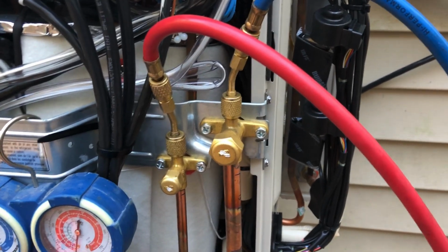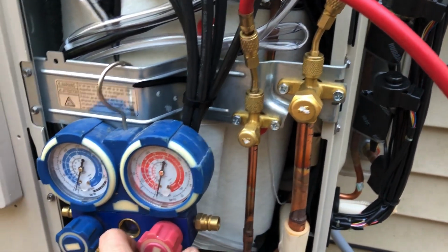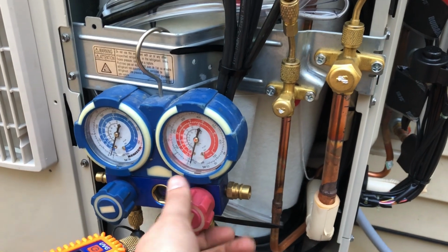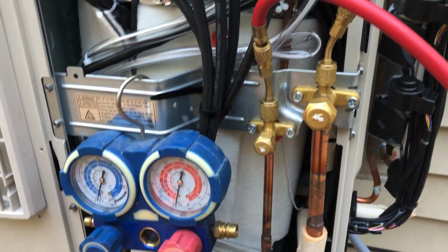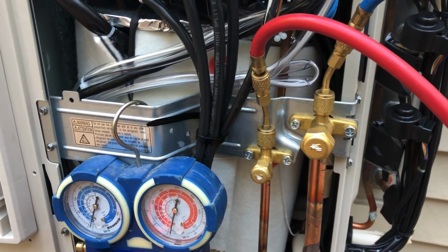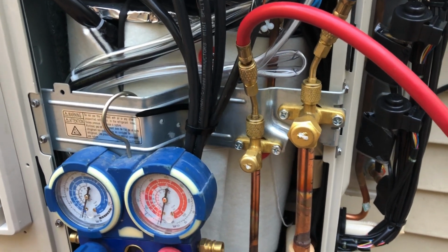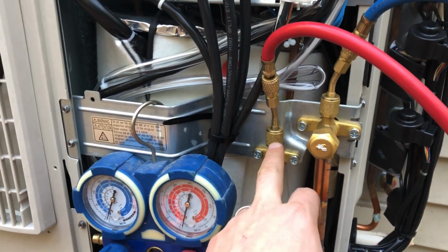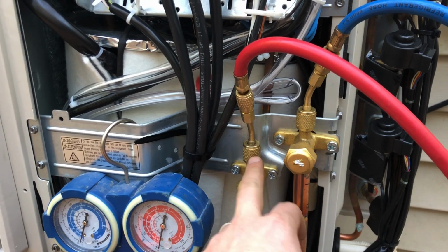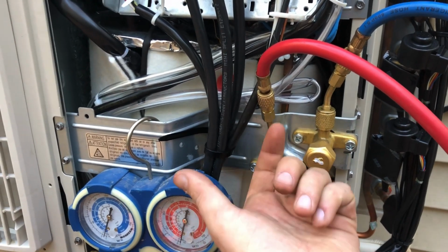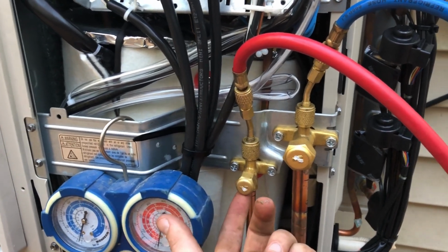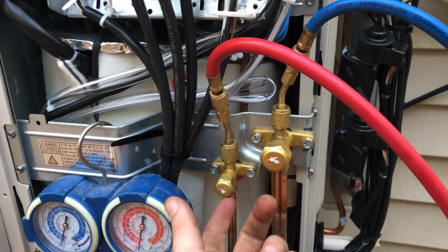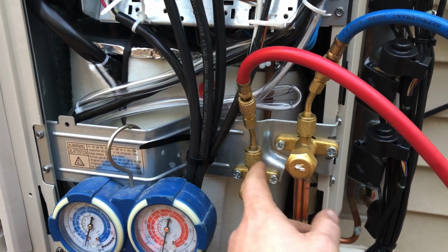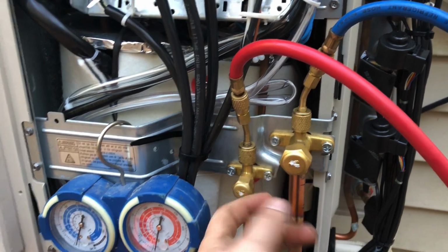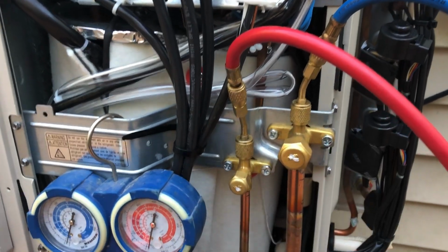Once you do that, you'll want to purge a little bit of HVAC refrigerant out, just a tiny amount, just to make sure that there's no air coming through. What I do is, you can actually just crack it right here. Once you crack it, after you've released the refrigerant, this is the key: only after the refrigerant is released do you then take these off, and you'll hear some refrigerant spray out, just a tiny amount. That's fine. So don't break the vacuum.